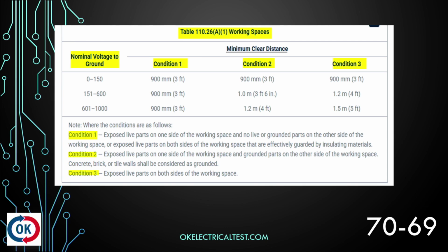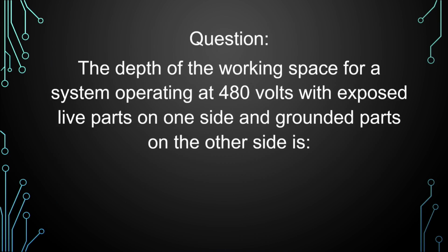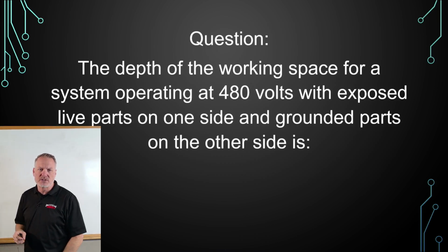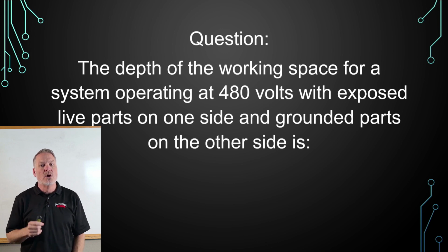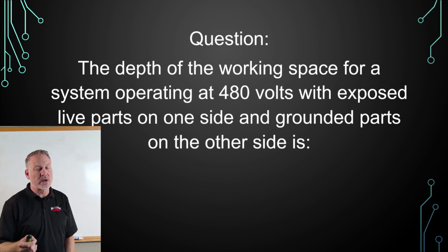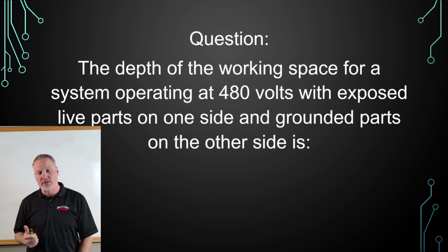So all of my electrical live parts are going to be in front of me. Condition 2 is I've got electrical live parts in front of me, but back behind me, everything is effectively grounded. And condition 3 is I've got live electrical parts in front of me and behind me. So when we look at this question, the depth of the working space for a system operating at 480 volts with exposed live parts on one side of the working space and grounded parts on the other side is going to be what? Minimum, right?